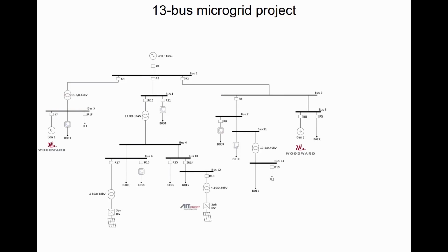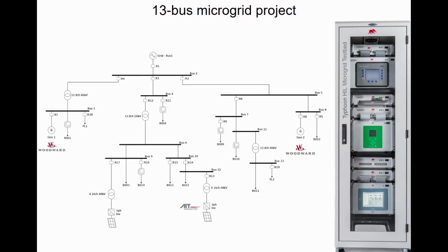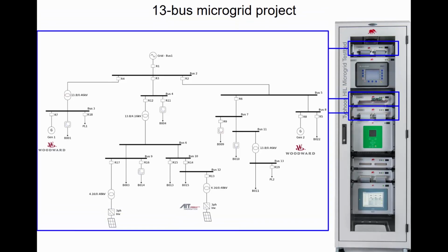The microgrid implemented is represented by this single line diagram. To simulate and test our controllers, we have a rack containing all the equipment used. All the power stage, or in other words, all that is represented by the single line diagram, is simulated in 3 HIL units. The power plant is a 3-feeder microgrid that operates at 13.8 kV and that is composed of dynamic and passive loads, transmission lines, transformers, relays, 2 diesel gensets of 1 and 4 MVA, and 2 photovoltaic inverters of 25 and 35 kW.